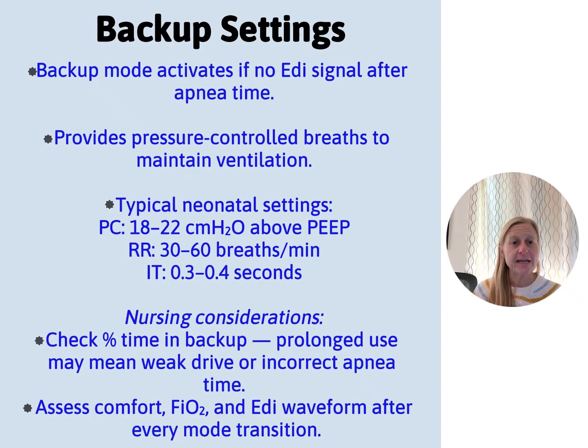We do have backup settings. So if there's no EDI signal after the apnea time, that means the phrenic nerve has not triggered the ventilator to say, hey, I'm going to breathe, give me a supportive breath. The vent's going to do it for you. It provides pressure controlled breaths to maintain ventilation. You've got your pressure control above your PEEP. You've got a respiratory rate, and you've got an I time.